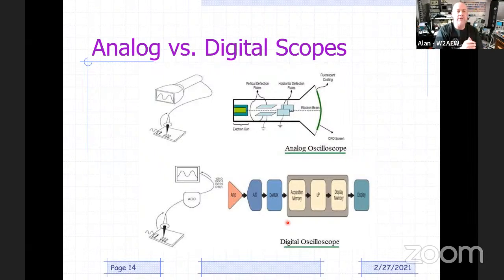And the old rule of thumb was that if you wanted to get within 2% of accuracy of your vertical amplitude for a signal, the scope should have 5 times the bandwidth of the frequency of that signal. Okay, so for a 100 megahertz scope, you're only going to get within 2% of the amplitude of a signal up to 20 megahertz, right? And above 20 megahertz, the signal amplitude is going to start dropping. It doesn't mean you can't see a signal beyond 100 megahertz or even at 150 megahertz. You'll still be able to see it. It's just going to be lower in amplitude. So you can't believe the amplitude, all right, because of that low pass filter characteristic. So that's a good point, Paul.